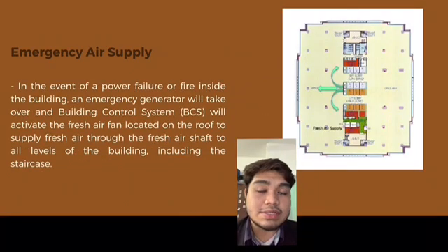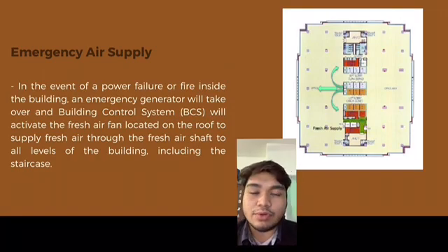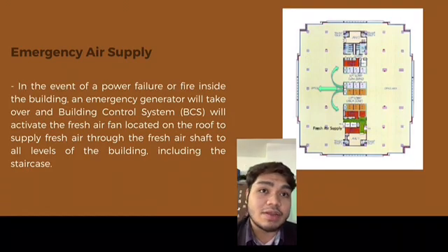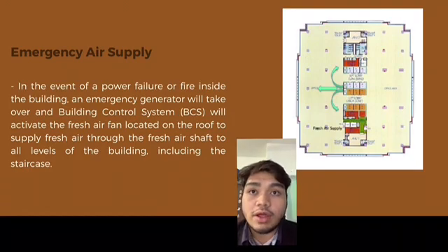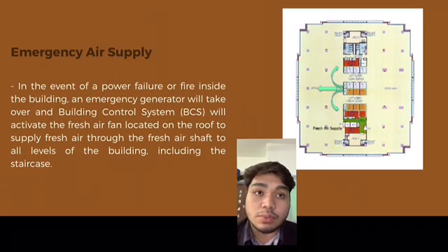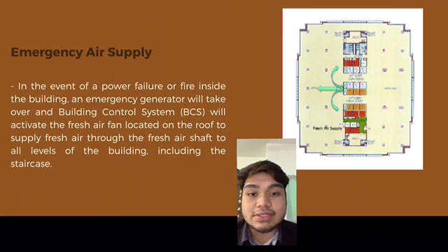The third one is emergency air supply. In the event of power failure or fire inside the building, an emergency generator will take over and the building control system (BCS) will activate the fresh air fan located on the roof to supply fresh air through the fresh air shaft to all levels of the building, including the staircase.